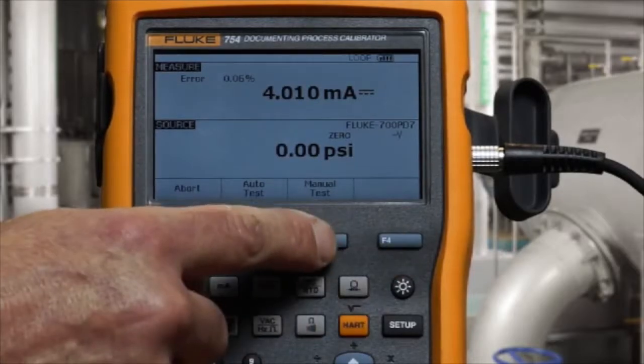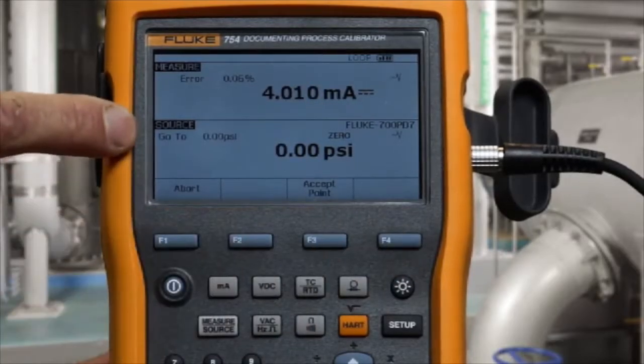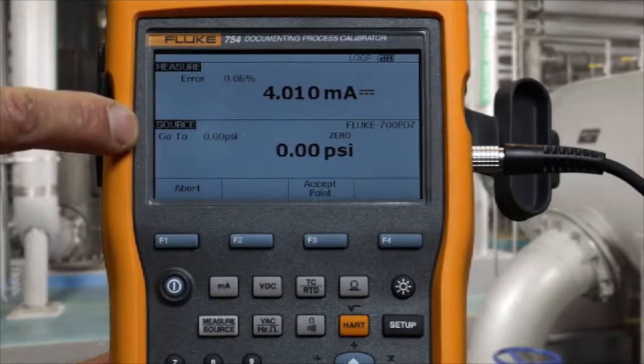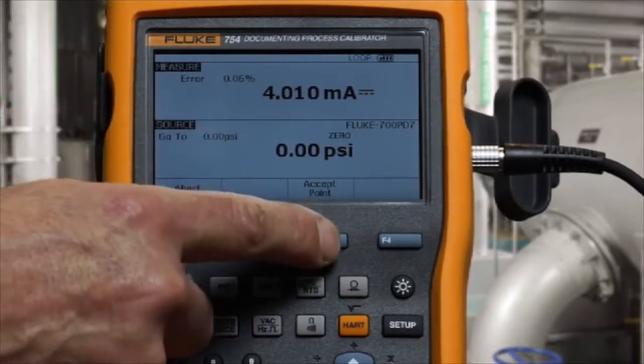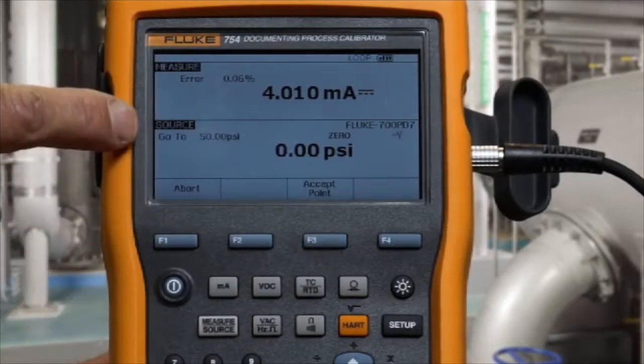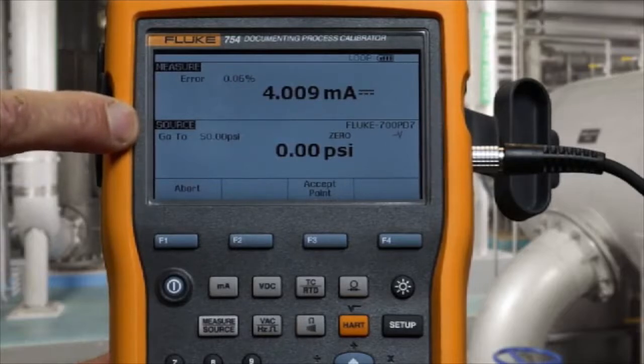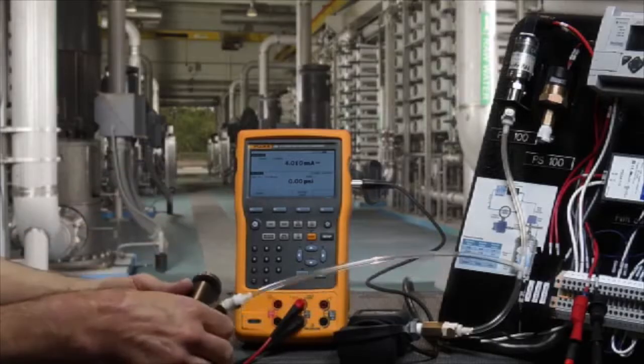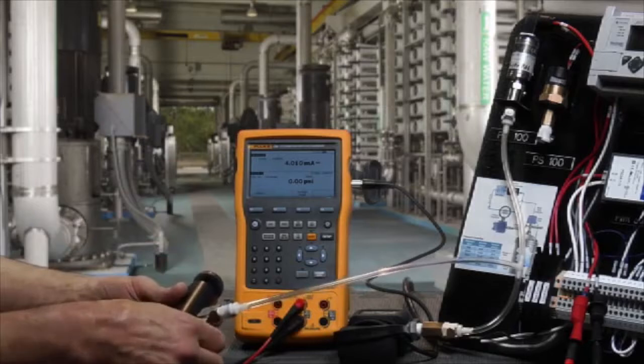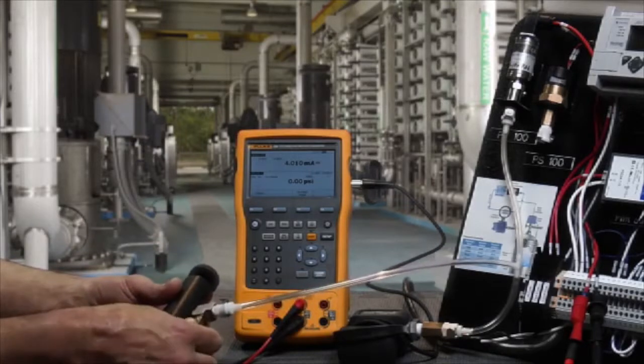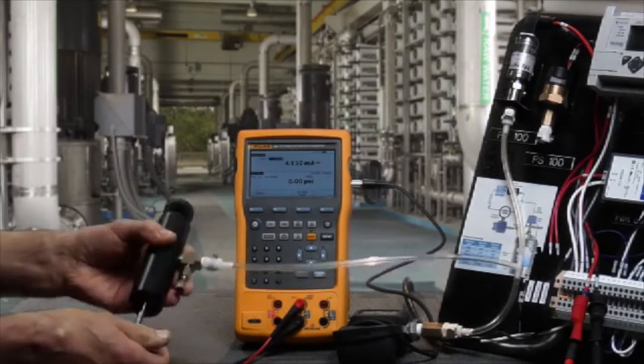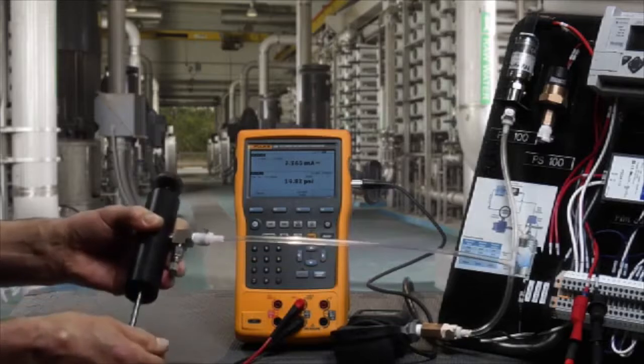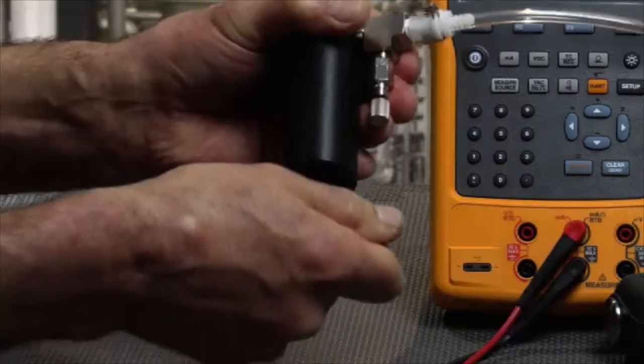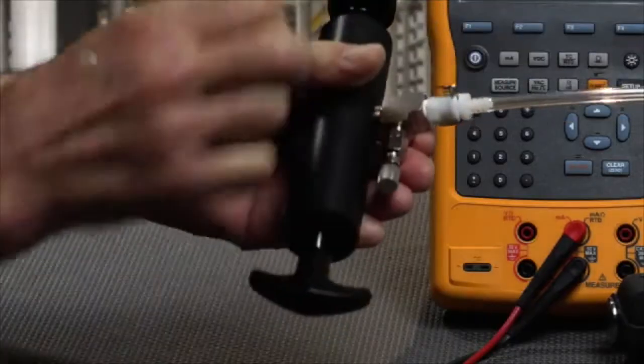When we select manual test, the calibrator will tell us the pressure to apply, and if we have the correct pressure applied, we accept that point. Now the calibrator asks me to go to 50 psi. I close the vent and pump to 50 psi. Use the fine adjust to dial in the pressure value.